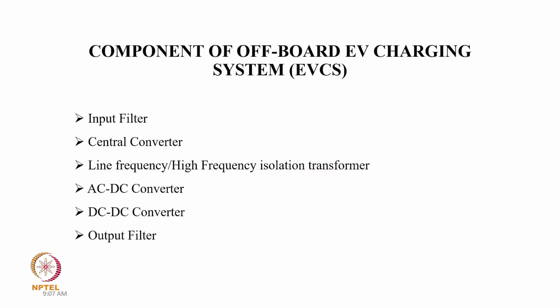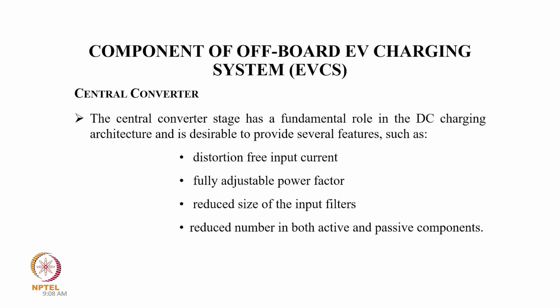So, coming to the components of an off-board EV charging system, typically there is an input filter, central converter, line frequency or high frequency isolation transformer, AC to DC converter, DC-DC converter, and output filter. Now, the central converter stage has a fundamental role in the DC charging architecture, and it is desirable to provide several features such as distortion-free input current, fully adjustable power factor, reduced size of the input filter, and a reduced number of both active and passive components.